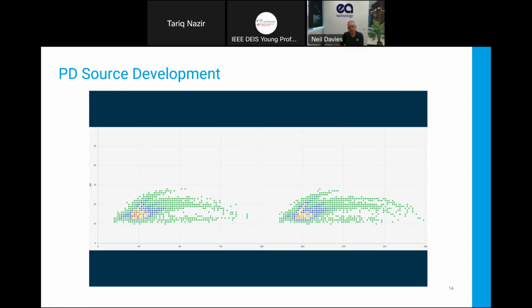And if you're testing a spot check at any specific stage on that, you could get a very different result. So if we're testing at this point here, we can see we've probably got multiple voids. We've got discharge up to around 28 to 30 dB. We're starting to get concerned about it. Just a few weeks earlier, we might have been in a completely different characteristic where we were down at 10 dB. There was very, very little indication of any serious defect.